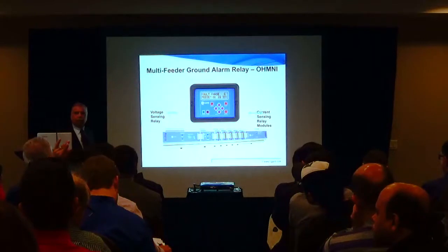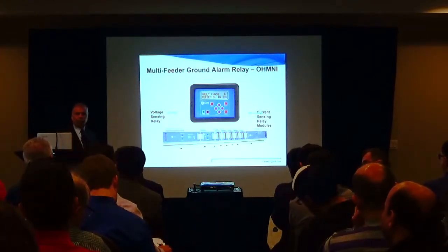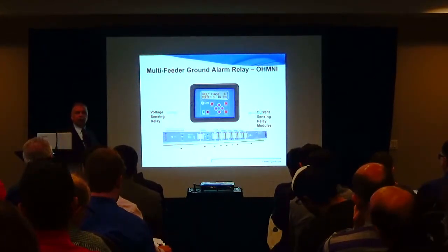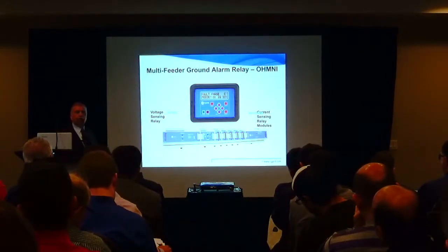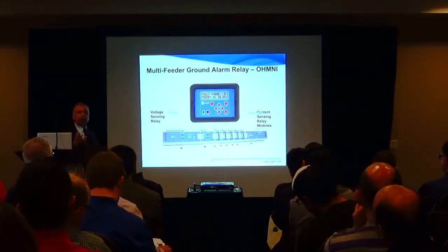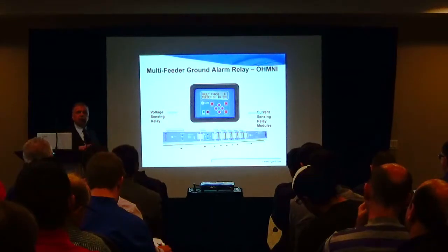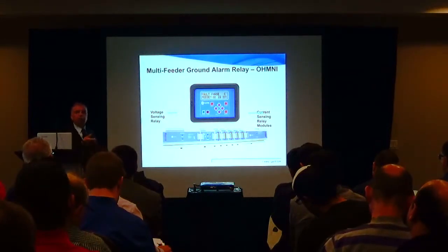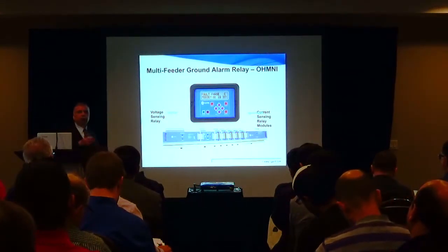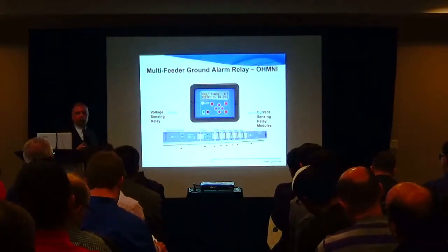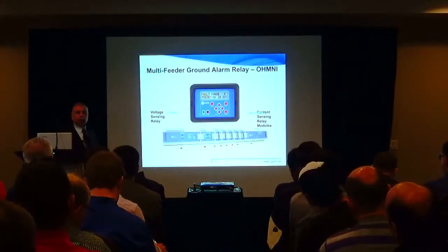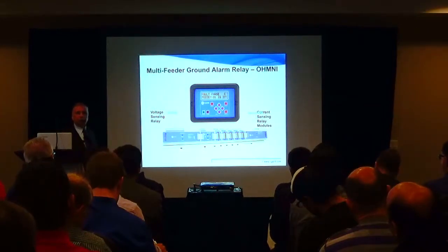Whoever your panel board supplier is will integrate that in its system. Which signals are available for PLC? You have a choice. You can take a contact into a PLC, or you can take a communication output. The output is Modbus, so if your PLC accepts Modbus, you're directly connected. If not, then you'll have to have a bridge from that to the PLC network. Your PLC may be using Ethernet or some other protocol, or 61850, so then you will have to convert from one bus to the other.